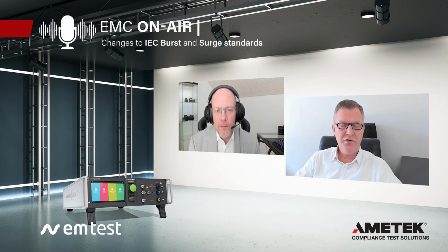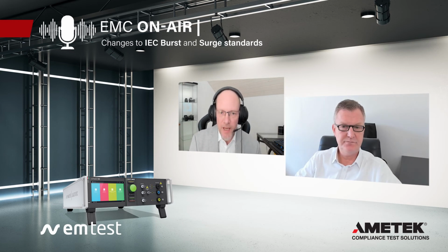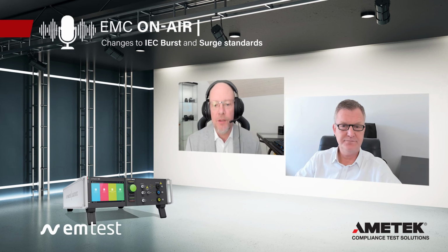Yeah, if you want to calibrate it, you need to use an 18 microfarad capacitor. In our device, it's integrated, and you can just enable or disable it. You need to use it from edition 3 on. You need to use it if you test surge on shielded cables. This was not specified in the old standard, but in the new one. So it's used during calibration or during testing with shielded cables. Correct. Yeah. Okay. Interesting.